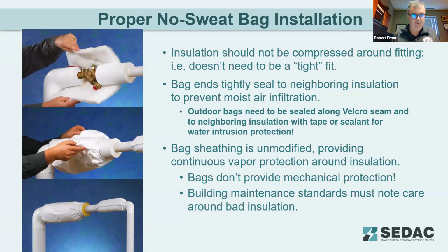Yes, Sean, that's a great point. As well as a lot of the building inspectors and people that we speak to at different functions, they say if it looks good, usually if the pipe covering looks good, it's probably going to be okay. The last slide actually shows with an infrared gun that if it's not done properly, there's a lot of energy that escapes. And those pictures in the last slide actually show that.